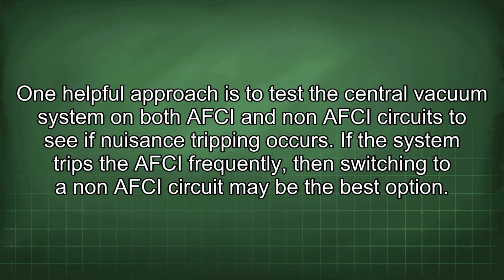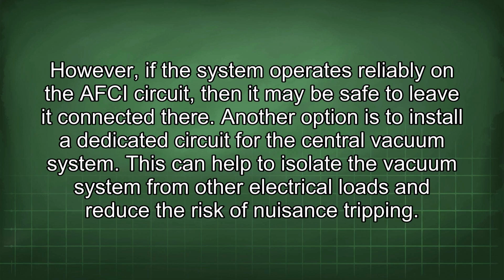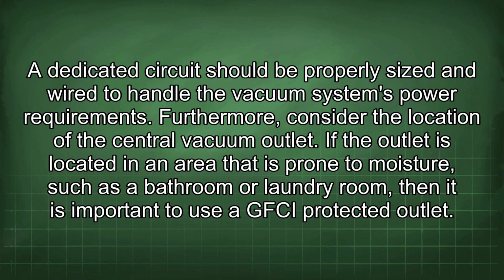One helpful approach is to test the central vacuum system on both AFCI and non-AFCI circuits to see if nuisance tripping occurs. If the system trips the AFCI frequently, then switching to a non-AFCI circuit may be the best option. However, if the system operates reliably on the AFCI circuit, then it may be safe to leave it connected there. Another option is to install a dedicated circuit for the central vacuum system. This can help to isolate the vacuum system from other electrical loads and reduce the risk of nuisance tripping. A dedicated circuit should be properly sized and wired to handle the vacuum system's power requirements.